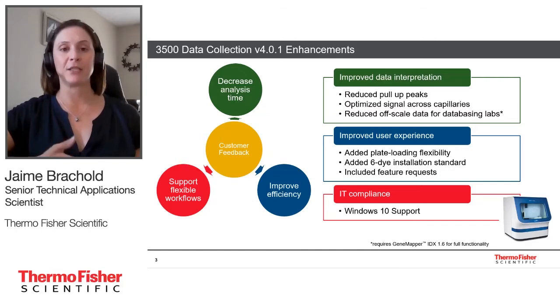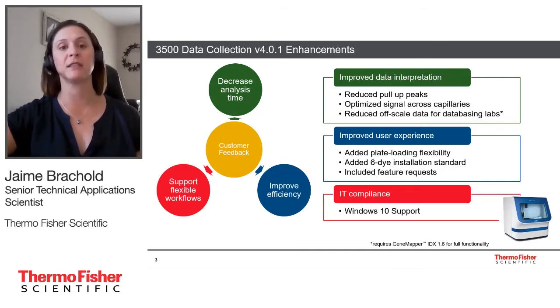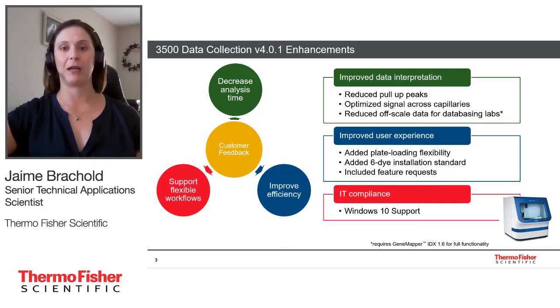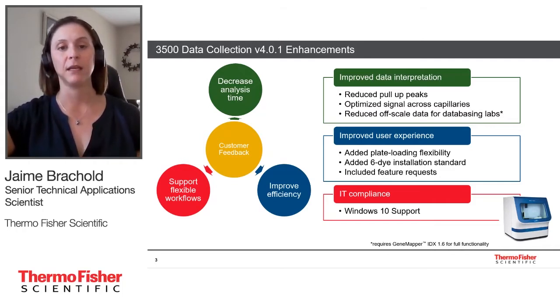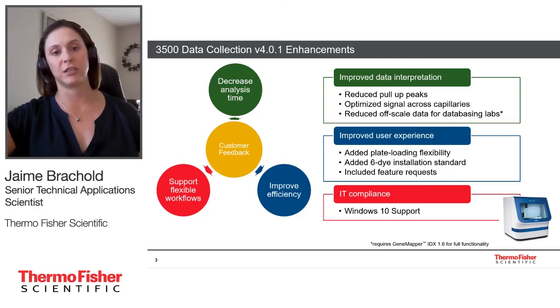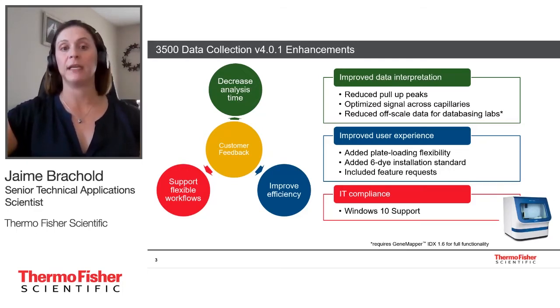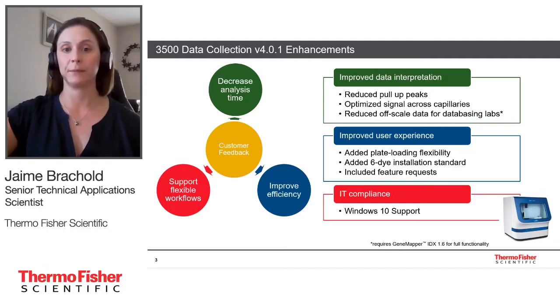Additional feature requests included being able to export the injection list, and a consumable log that's easy to read showing when consumables were changed and by whom. There is a full list of all new features in the data collection user bulletin. This data collection version 4.0.1 is Windows 10 supported.